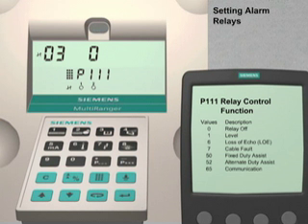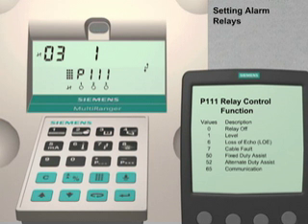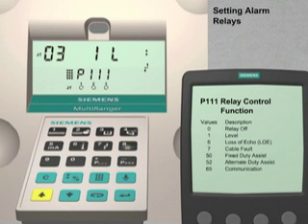We will set relay number 03 to be our low level alarm. As shown in the programming chart, a general level control function can be used to provide relay control based on the liquid level in the vessel. This control function has a numeric value of 1. Enter 1 followed by the enter key to assign this function to relay number 03. To set relay number 03 to be a low level alarm, press the units key. The Multiranger will display a double up arrow to indicate that we are setting an alarm. Press the up arrow key twice. The Multiranger will now also show a single letter L for the low level alarm. Press the enter key.